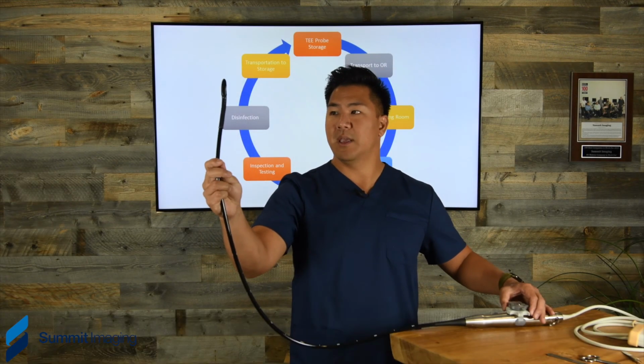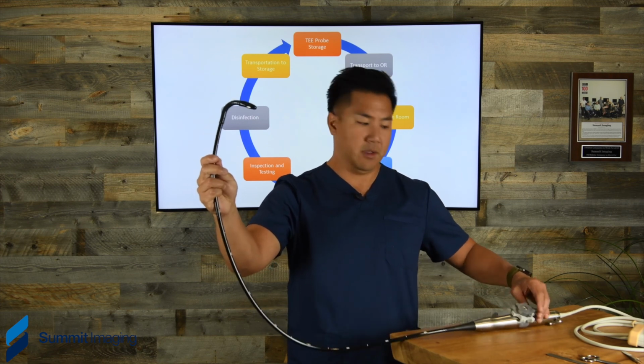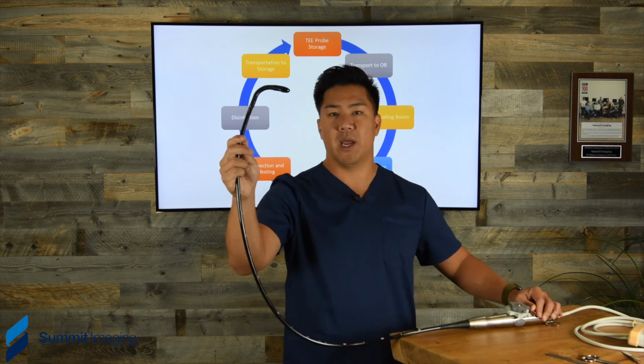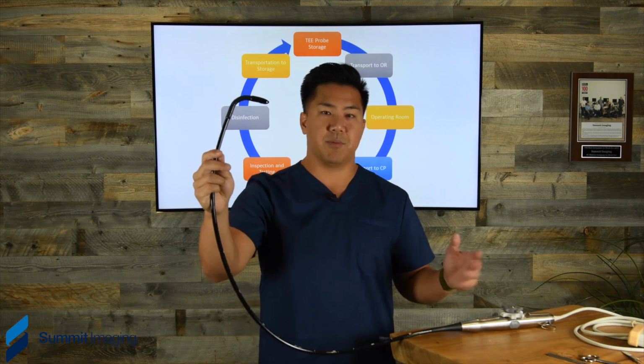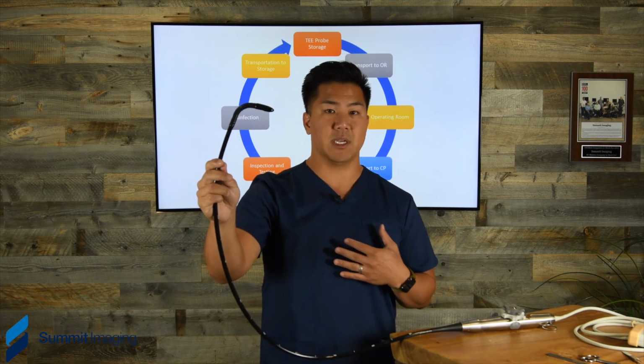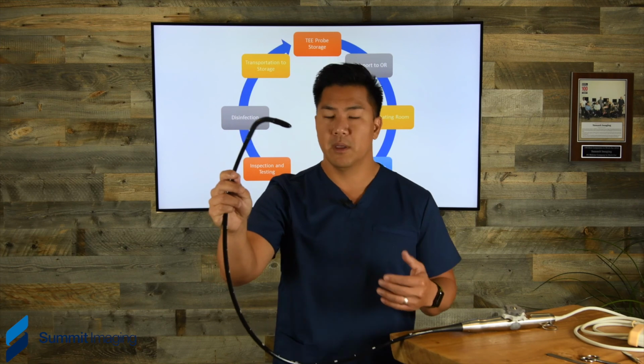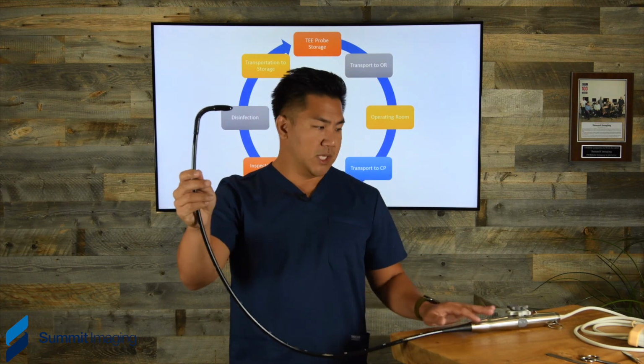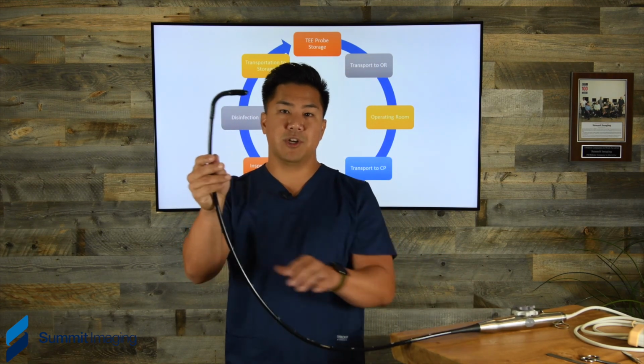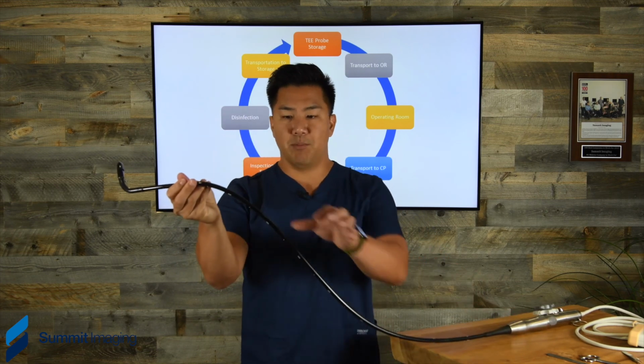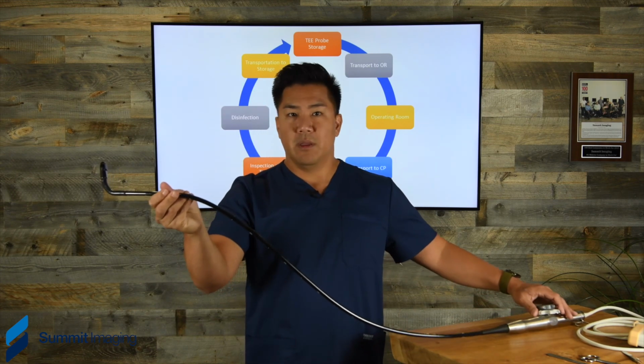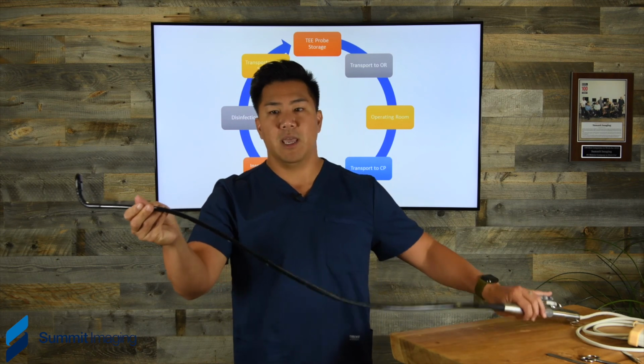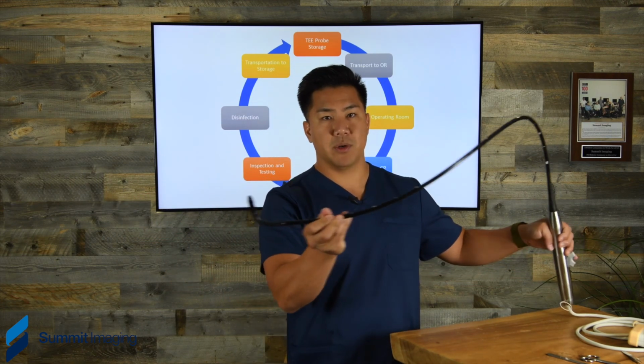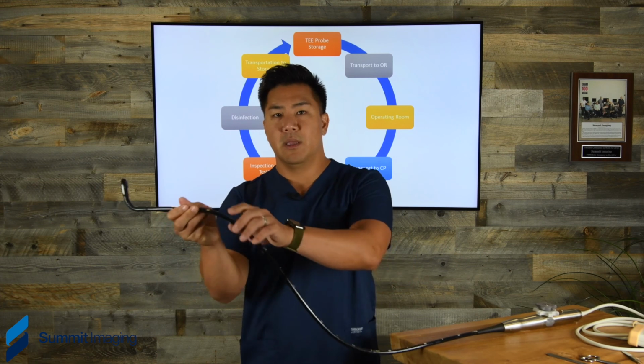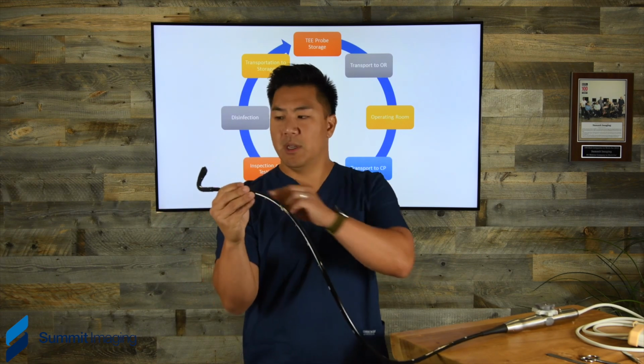these probes can lock. So I can lock this probe into a 90-degree position. This allows a probe to be articulated inside the patient to get a great picture of the heart. But even with the use of a bite guard, which would, traditionally, if this is inside a patient, be at the mouth, by not unlocking this and pulling the transducer out, it will actually hit the back of the molars of the patient and scrape that lens pretty good.